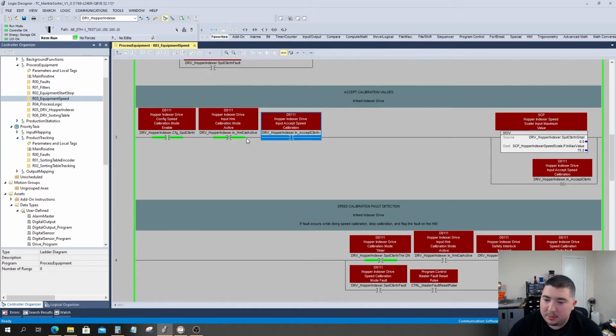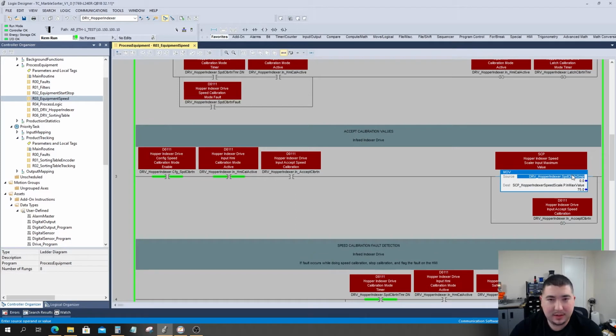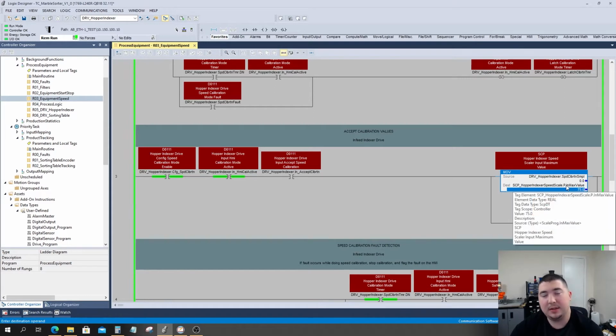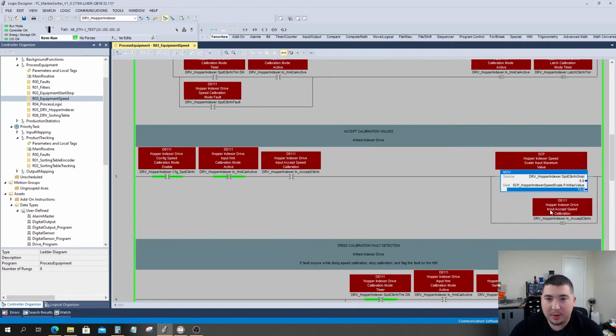This is the rung where we can accept the value. So the idea with this is that the user could then look at the HMI and say, okay, is this a number that makes sense? Do you wish to accept the value? And if the user selects that they do want to accept, we will then change our sample speed into our max output speed. And this is for the SCP instruction that scales our output speed with our real analog output speed. This way our final speed that we command is relatively close to or exactly the same as what we want it to be in reality.